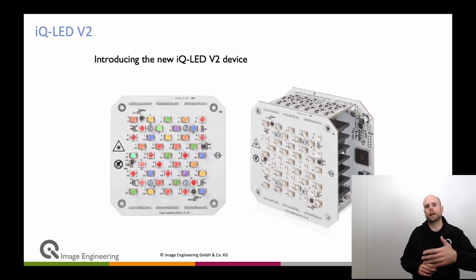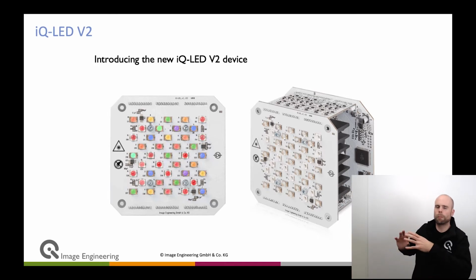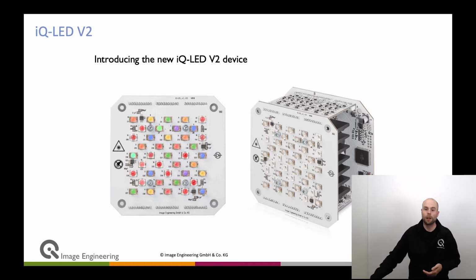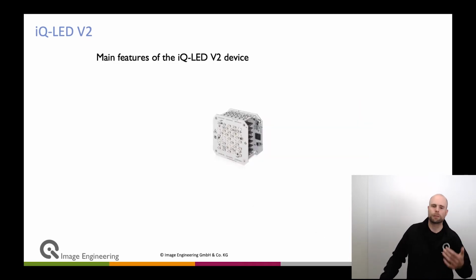So if you run iQ-LED technology, for example, on a production line, in a 24/7 environment, maybe every other week, and after a while maybe you can switch to every month, you would do a recalibration that the device can perform by itself. With that, you are sure that you have a very stable condition, and it will always go back into the same conditions. So that is extremely powerful.